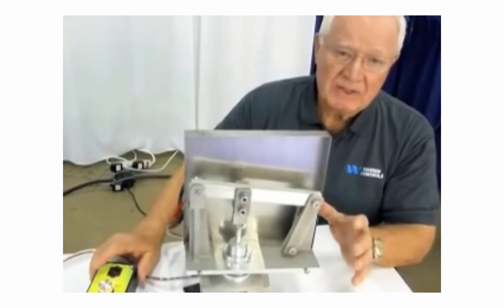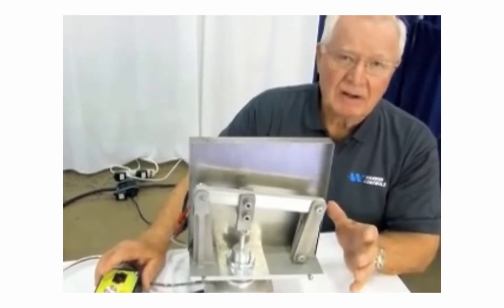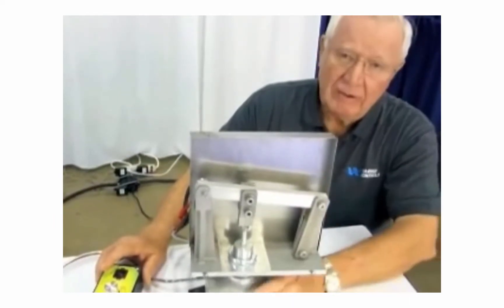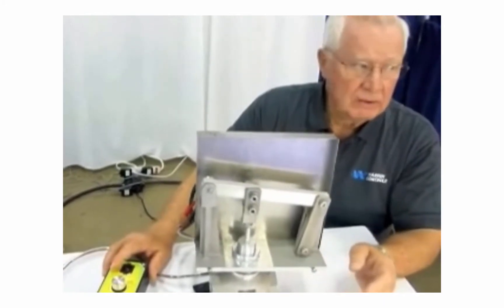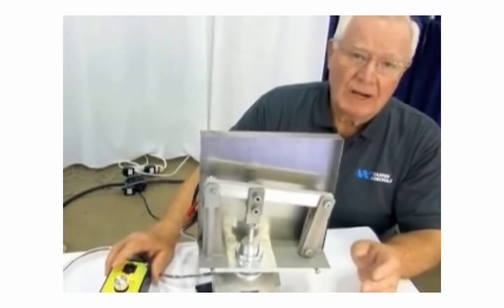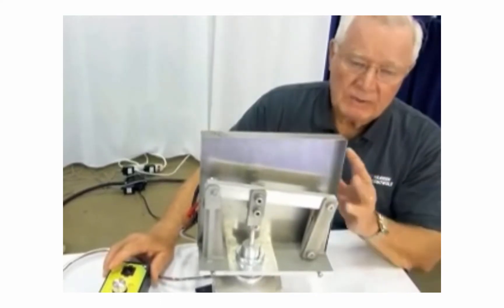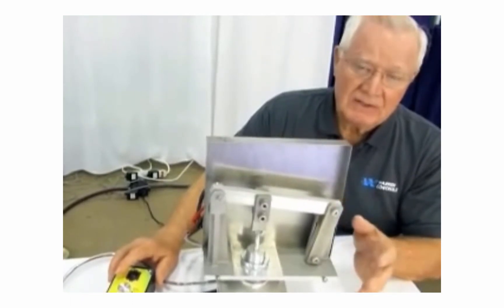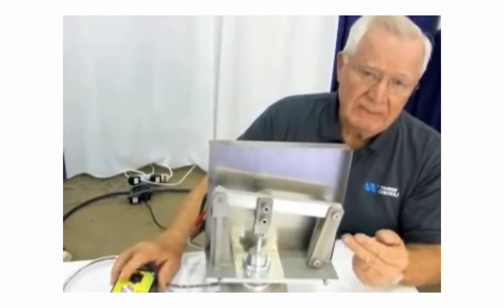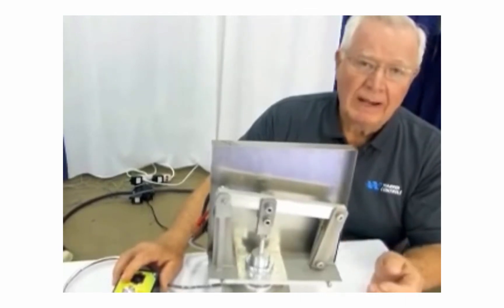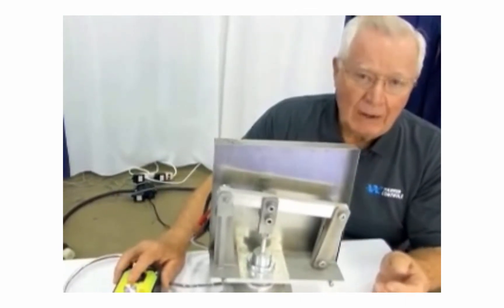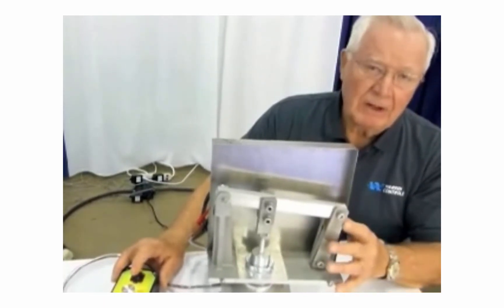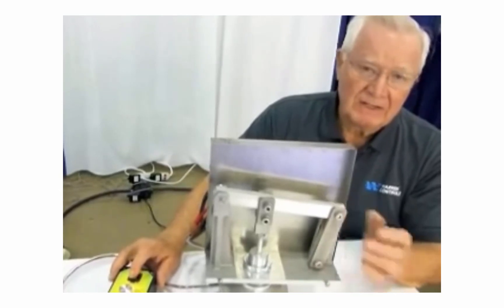The main point that this accomplishes is it saves the cost of producing air. So that for an equivalent size control valve of this size here, or two inch or three inch, it might cost up to approximately $800 a year for air. Whereas with the electric system, it will cost about $10 a year. So the initial savings is significant, as well as the savings of being able to run a pair of wires as opposed to an airline, which typically will leak right from the very beginning. So all in all, you've got cost savings, functionality is not being compromised, and flexibility is optimized.